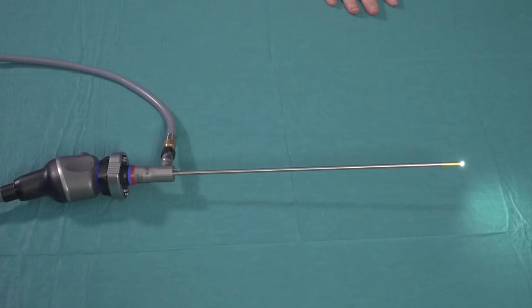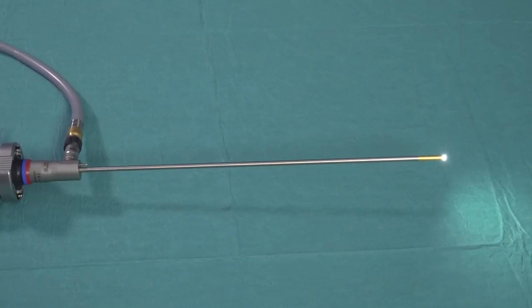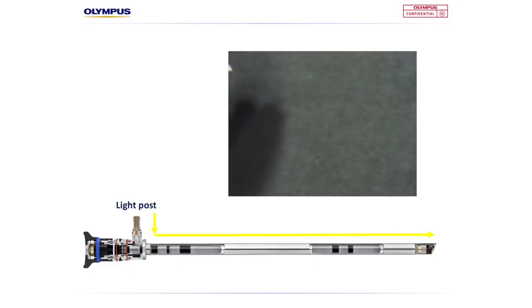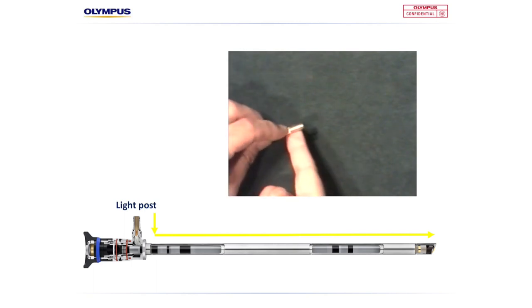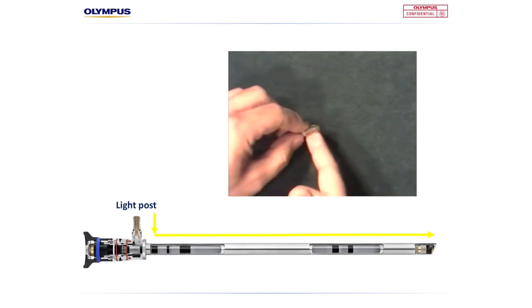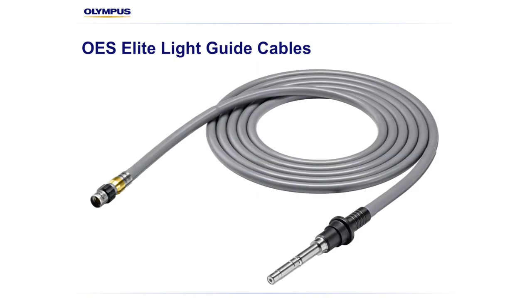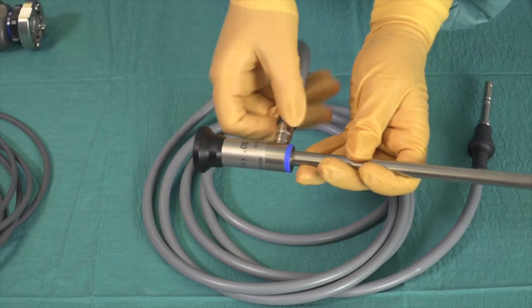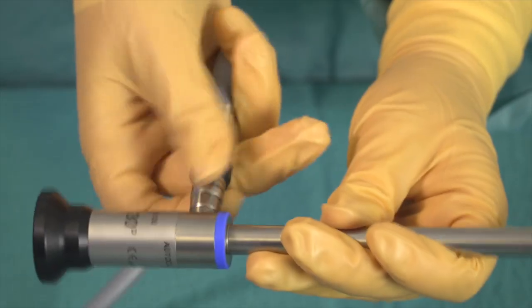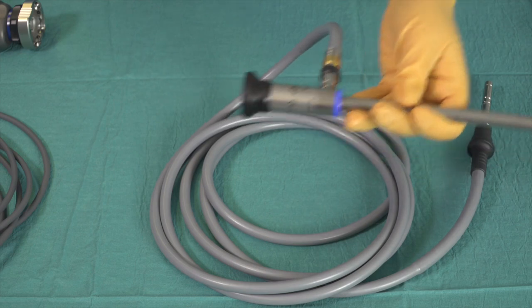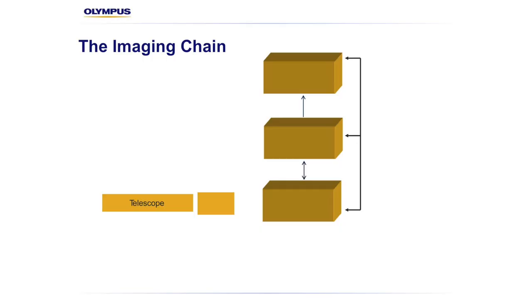But telescopes don't just relay the image — they also help us deliver light into the cavity within which we're observing. This is crucial when working within the body. Light is delivered via a bundle of tiny fibre optic strands which run along the shaft or tube of the telescope. When using a rod lens or fibre optic scope, a light guide will also be required to carry the light into the telescope from the surgical light source. The connection of the light guide onto the telescope is a simple thread twist, though a competitor telescope or light guide may require an adapter. This leads to the next component of the imaging chain: the light guide and light source.